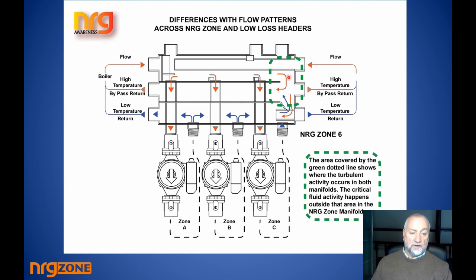So if it's neutral here, because the boiler pump is delivering in and the boiler pump is drawing back from there, and your expansion and cold feed are joined here, you've got the most perfect location to create a very healthy circulated heating system from that location. So this pump can draw from the neutral point, this pump can, and this pump can. Likewise, the return goes back.